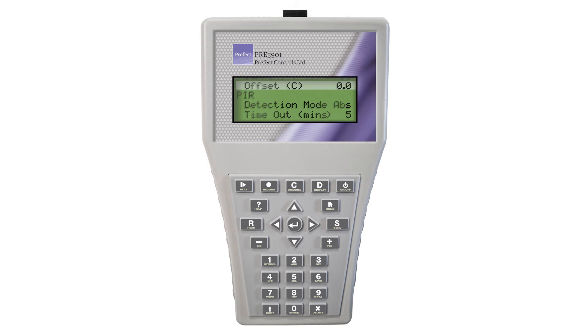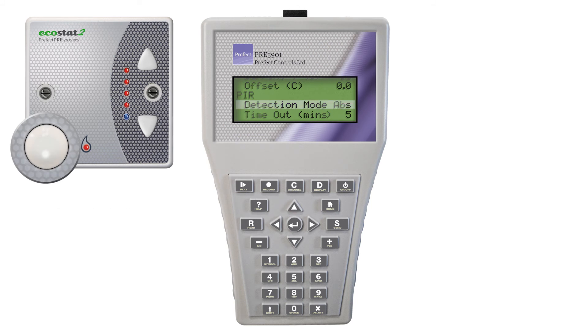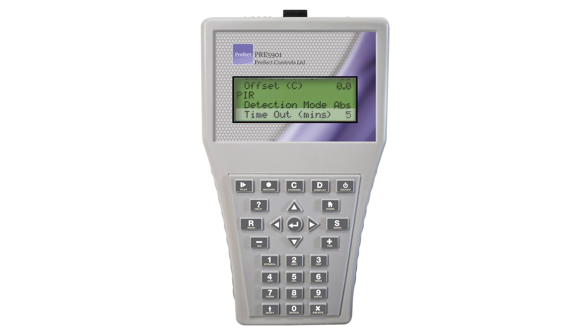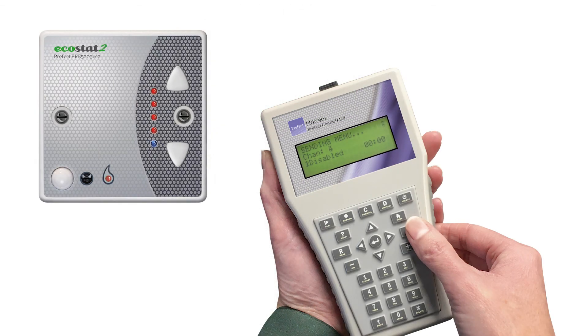The PIR can be set to absence or presence detection. Use the plus and minus buttons to select the preferred mode — ABS is displayed for absence and PRES for presence. Timeout sets the interval before the PIR switches the heater off when no movement is detected; this only applies when absence mode is selected. When you are happy with the settings, point the handset at the thermostat in the room and press the send button. This will send the highlighted parameter to the wall unit. To send all the parameters in the menu, press and hold the send button for 2 seconds or more. An audible beep lets you know that all settings have been sent to the thermostat.